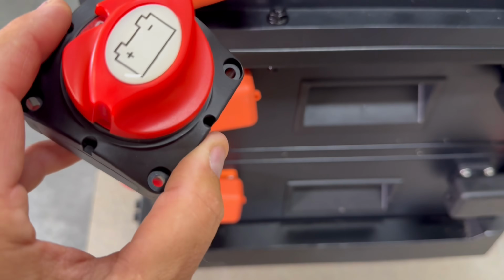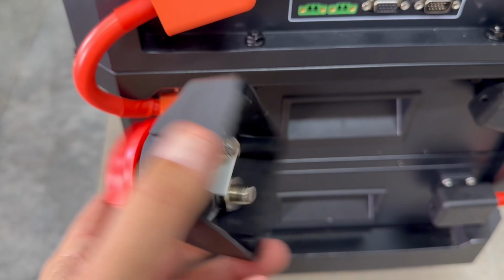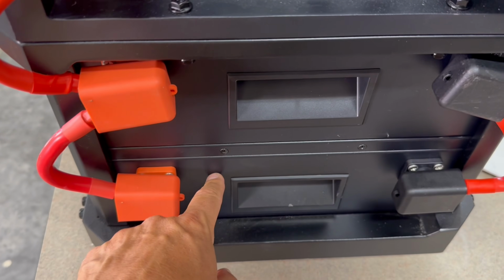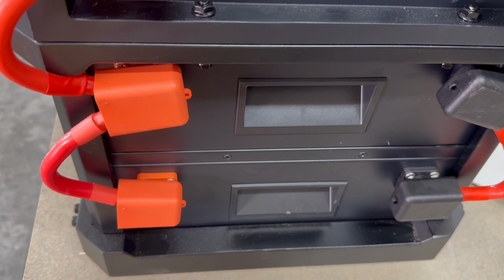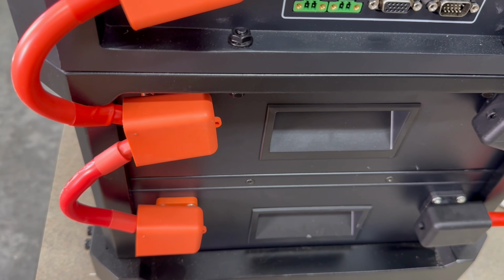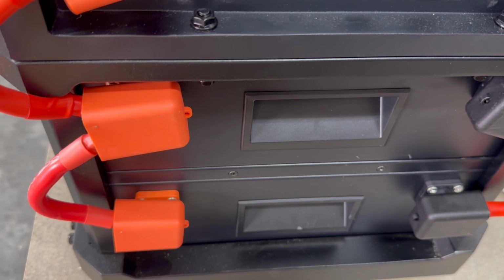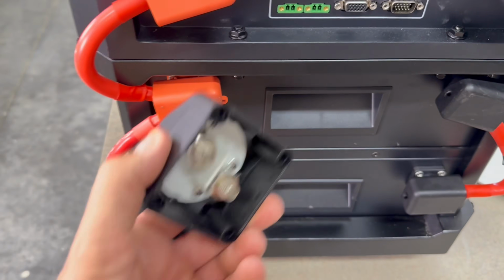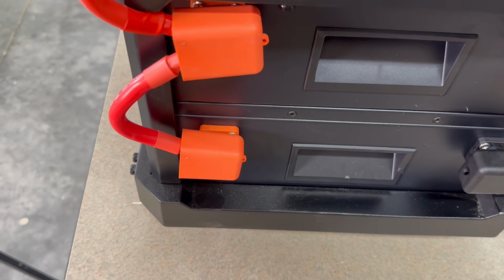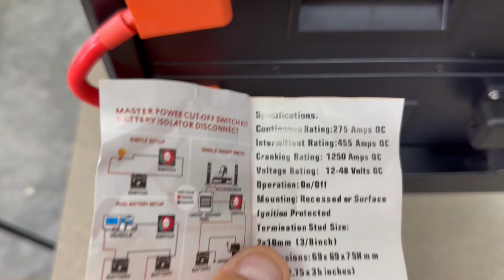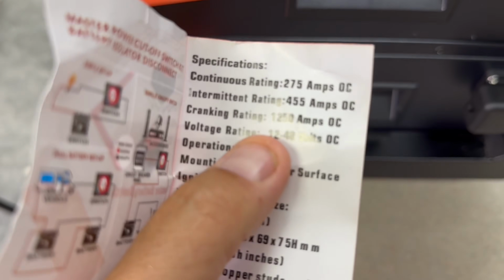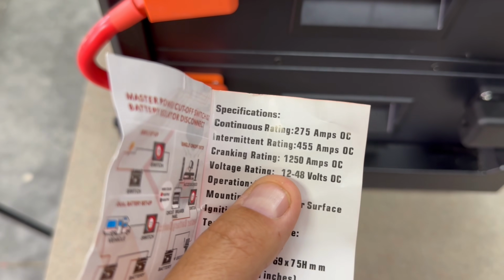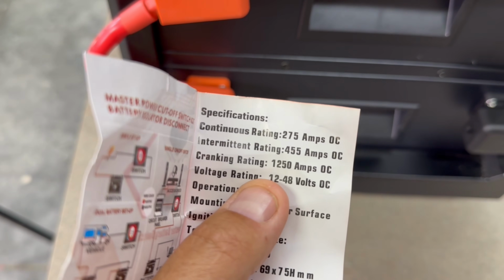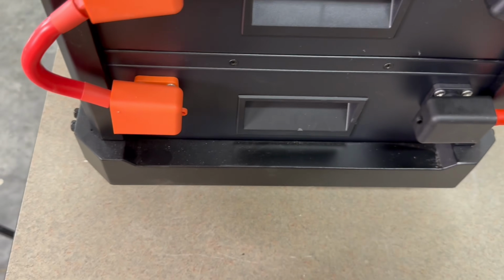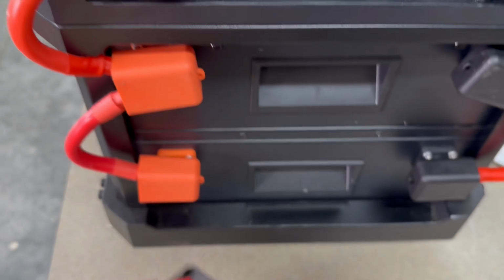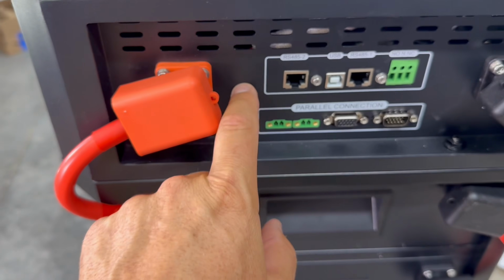My problem with these is that they are not rated for over 48 volts. And as you guys well know, these packs are 16 in series, so you're talking 51.2 volts nominal, and you can go all the way up to 58 volts. That's well above the rated voltage for these switches. Hold on, I have the little thing that came with it. You can see there, right on that line, 12 to 48 volts DC. So it does not go to the voltage that this pack is going to be rated for. This is not a proper means of disconnect between the batteries and the inverter.